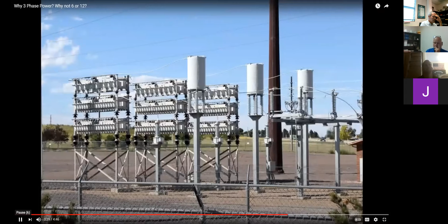With a 6-phase line, there would be 6 circuit breakers and 6 bus bars. With 12 phases, there would be 12 circuit breakers and 12 bus bars. So the complexity of coupling it - it's called a high phase order line - into a substation sort of defeats the economics of it. There you go, you can pause it there.